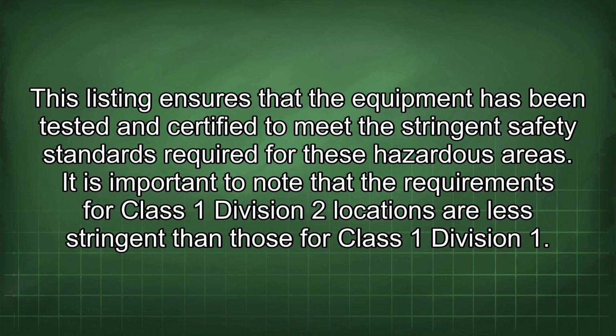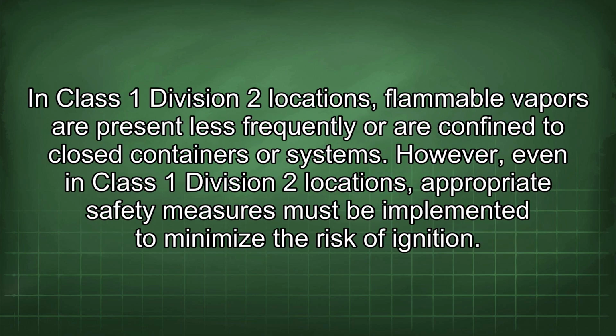It is important to note that the requirements for Class 1 Division 2 locations are less stringent than those for Class 1 Division 1. In Class 1 Division 2 locations, flammable vapors are present less frequently or are confined to closed containers or systems. However, even in Class 1 Division 2 locations, appropriate safety measures must be implemented to minimize the risk of ignition.